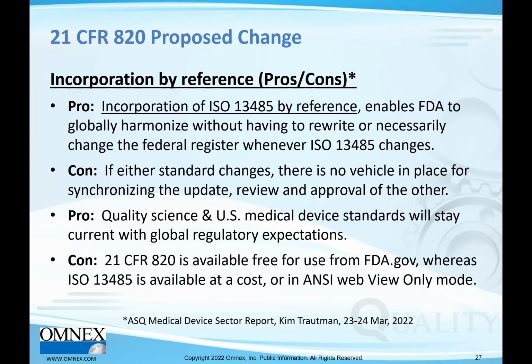Another con for this incorporation by reference is that 21 CFR 820 is currently available free for use by anybody from FDA.gov, whereas 13485 is only available at a cost or in a web view only mode. So you can view it, but that's about it. You can't copy it because of the copyright laws. You need to buy it and you need to have it available. So that's another con for how this is being done. There may be areas in which things will change, but they haven't been worked out as far as I know.